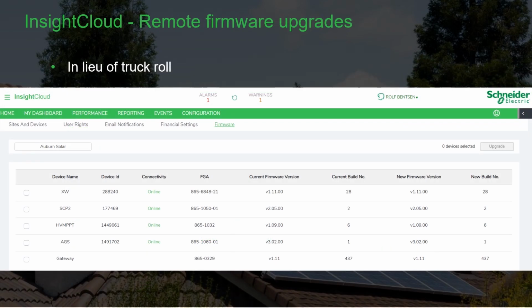Probably the most valuable feature to installers is the ability to perform firmware upgrades remotely. It's always the best practice to have the latest firmware in all devices. Now you can perform firmware upgrades from the comfort of your own office. By clicking on the Firmware tab, you will see a list of all devices, their current firmware revision, and new firmware available. You can see here that InsightLocal, in this case the Gateway, and the XW Pro need updates.